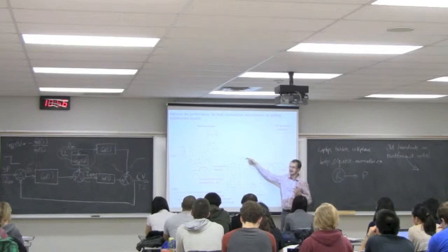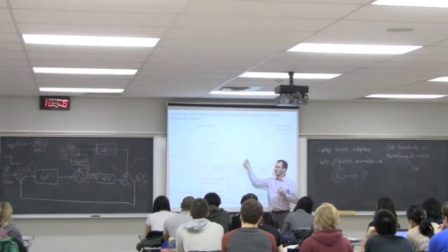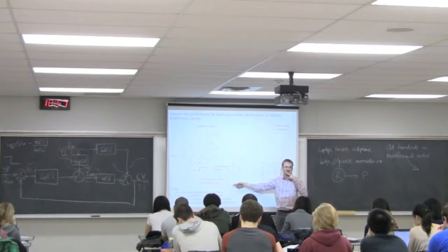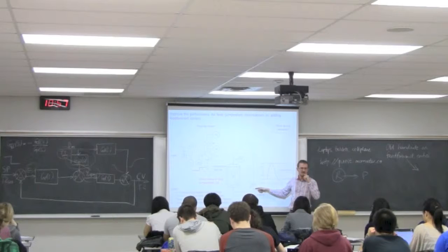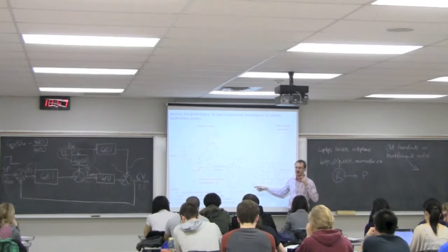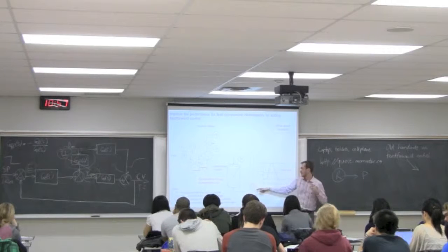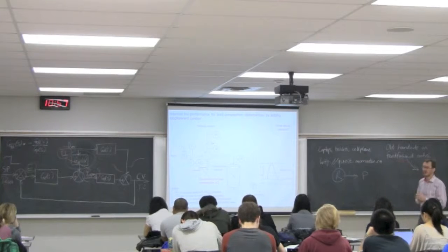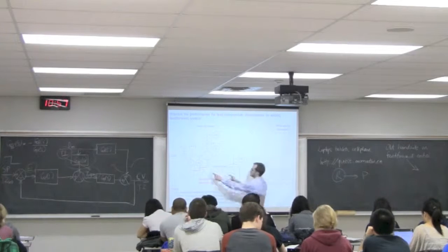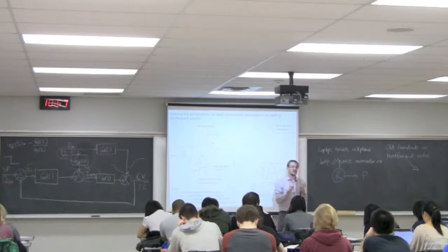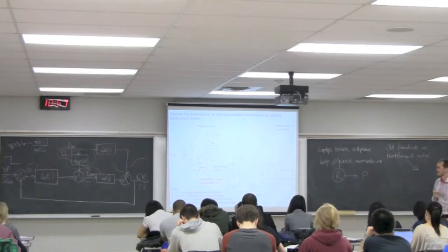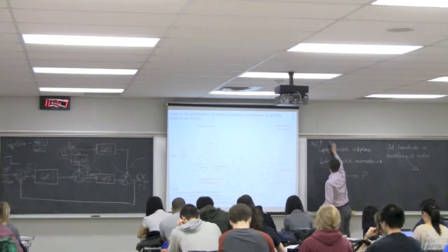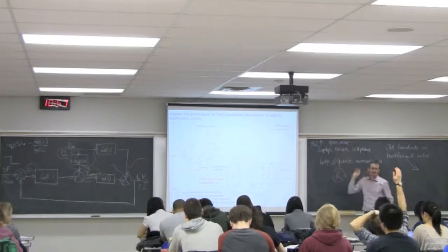What's going to happen to T3? Close the valve. It drops. Lower temperature, what happens in the reactor then? Slower reaction, lower kinetics. What's going to happen to AC1? Okay, so did you make the right decision? AC1 is going to go up, right? So lower kinetics, you've got more unreacted material, it's going to rise. So that was the wrong direction. Opening the valve would have been a better choice. So A2 goes up, open the valve. A2 goes down, close the valve. So that's your preemptive action. If you were the feedforward controller, you should expect to see that. So let's make a note of that up here. A2 goes up, you should open the valve. If our solution doesn't show that to us, we've done something wrong.